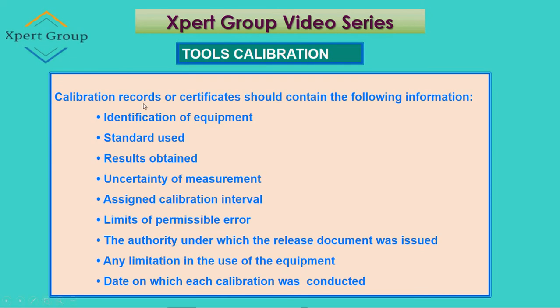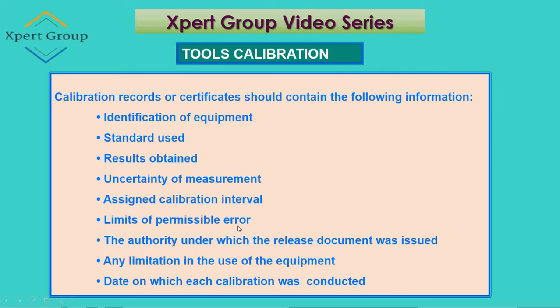Calibration records or certificates should contain the following information: identification of equipment — what type of equipment it is and its specific identification; the standard used — on which standard the calibration is based; result obtained — what the results were after and before the calibration; uncertainty of measurement — if there is any uncertainty, that needs to be mentioned; and assigned calibration interval — when the next due date is coming and when it was last completed.